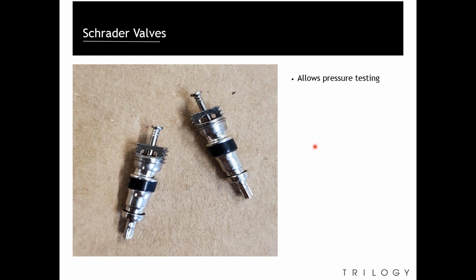Outside those service ports, we have the Schrader valves. This allows us to pressure test. This prevents refrigerant from leaking, but this also is one of the main culprits for leaking refrigerant. So we always want to put our caps back on those service ports when we're done hooking up our gauges, to reduce the risk of refrigerant loss.